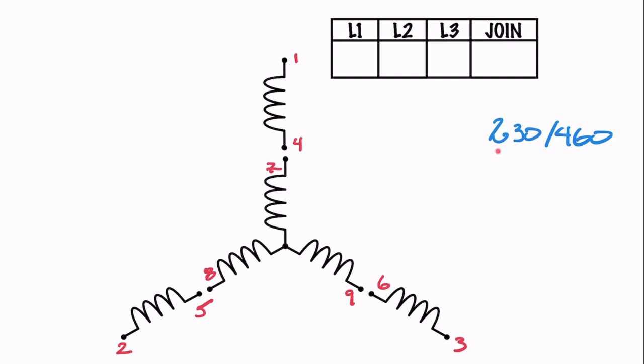Now we need to figure out whether we're connecting to a lower voltage or a higher voltage, which means we're going to be connecting these leads in parallel or in series. We're going to start with the lower voltage first, because I find it's the trickier one to deal with. When we're dealing with voltages in parallel, the key thing to remember is that parallel voltages remain the same. So we have to connect our windings so that each pair is in parallel.